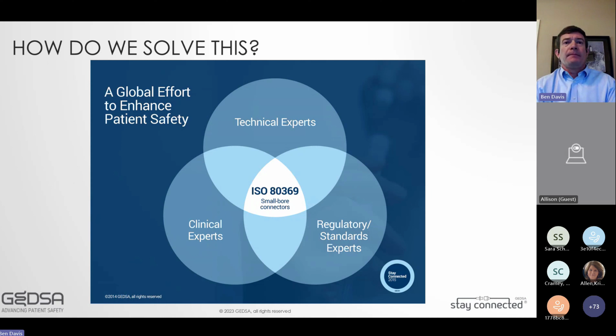The main drive or goal of that effort was to make mechanically engineered connectors that were incompatible with other areas of therapy, so that no connectors within the series would cross connect with one another, to really try to minimize the risk of a misconnection event occurring. Of course, today we're talking about the enteral section, which is ISO 80369-3, more commonly known as ENFit, and then the neuraxial section, which is ISO 80369-6, commonly known as NRFit. Those are the two we're focusing on today, but those aren't the only two.